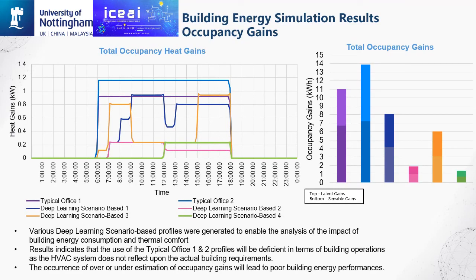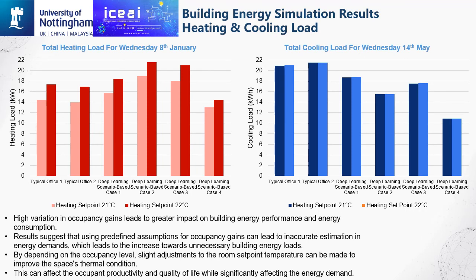The diagrams here show that various deep learning profiles were generated to analyze the impact on building energy consumption and thermal comfort. Results indicated that the use of typical office profiles 1 and 2 would be deficient in building operations, as the HVAC system does not reflect actual building requirements. Over or under estimation of occupancy gains leads to poor building energy performance. Results for predicted heating and cooling loads during typical winter and summer days suggest that using predefined assumptions for occupancy gains can lead to inaccurate energy demand estimation, increasing unnecessary building energy loads. Furthermore, slight adjustments to room set-point temperature based on occupancy level can improve thermal conditions and affect occupant productivity and quality of life while significantly affecting the energy demand of the building.